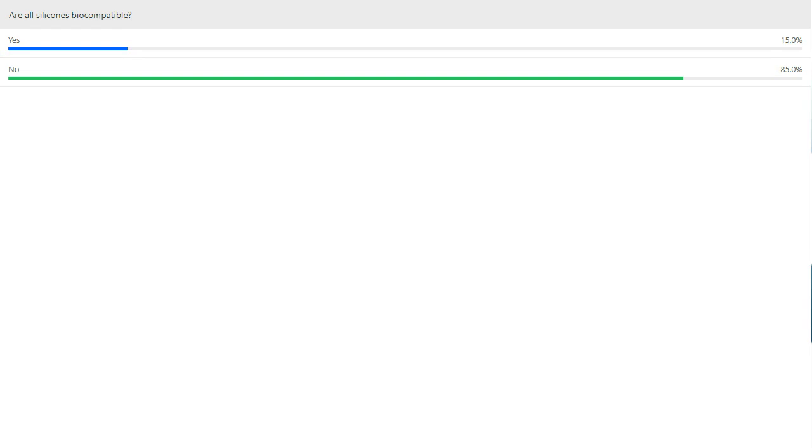So that is correct. All silicones are not necessarily biocompatible. Now, medical grade silicones normally will be. However, it will depend on the amount of testing that backs them. Some amount of testing can be leveraged for the manufacturer, or the end user can conduct their own testing. Flexan leaves a final responsibility regarding biocompatibility to our customers, because you never know how it will actually be used in a finished device.